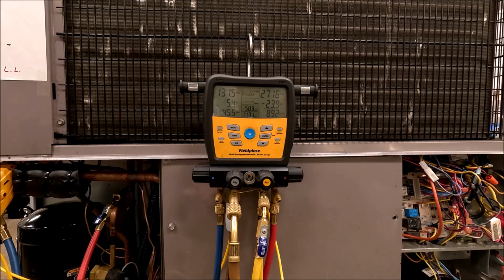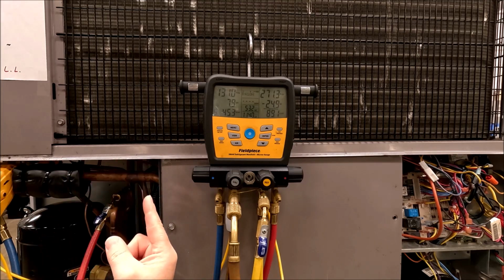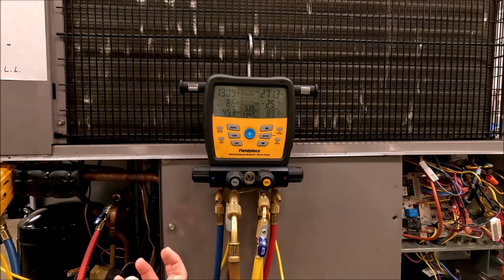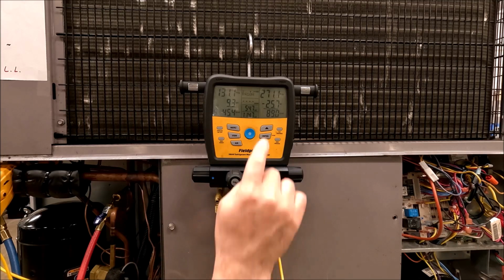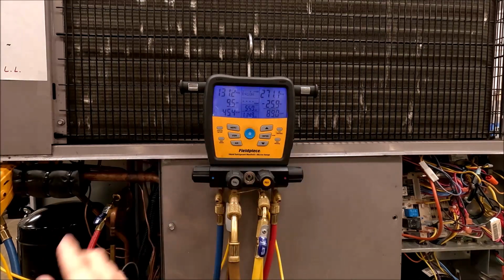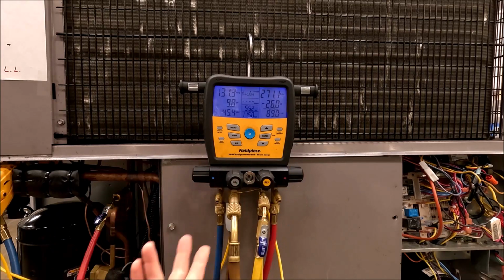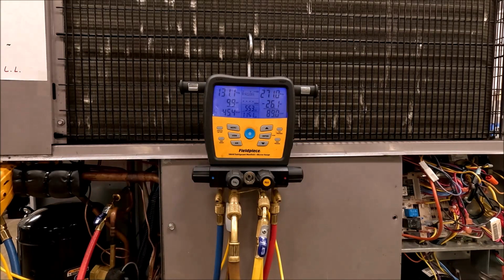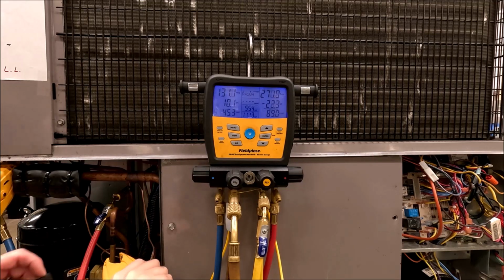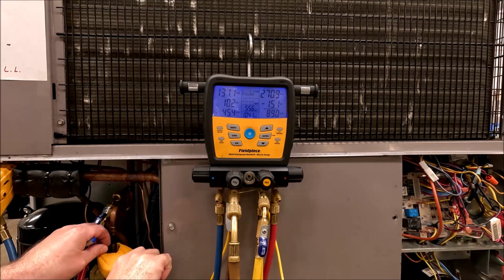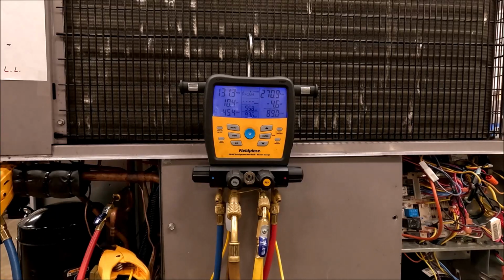Know the numbers you're supposed to get. Know where, because it's not just put the big number on top and do an easy subtraction problem. Superheat is the vapor line temperature minus your evaporator saturation temperature. And subcooling is the saturation temperature of your condenser minus the liquid line temperature. If you put it wrong, you get these fancy digital gauges and it says negative 26, and that ain't nowhere near right. So put it in the right spot and this thing will easily pick it up.